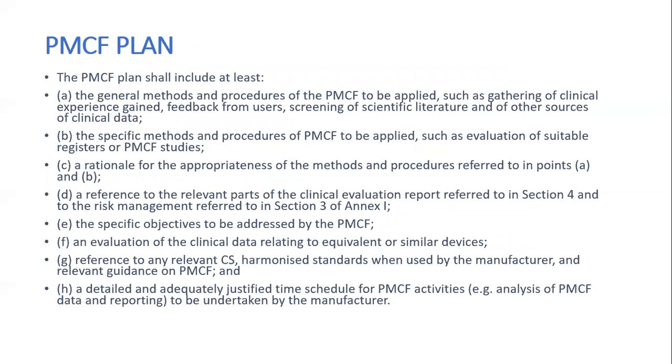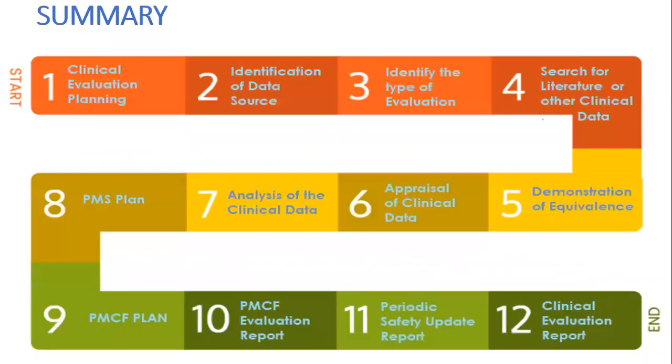What should the PMCF plan include? It should include at least the general methods and procedures of PMCF to be applied, such as gathering of clinical experience, feedback from the users, and screening of scientific literature and other sources of clinical data. It should also include the specific methods and procedures, such as evaluation of suitable registers or PMCF studies, the rationale of the appropriateness of the methods and procedures, specific objectives to be addressed by PMCF, evaluation of clinical data, the harmonized standards, and the time schedule of the PMCF activity where you are going to perform the analysis.